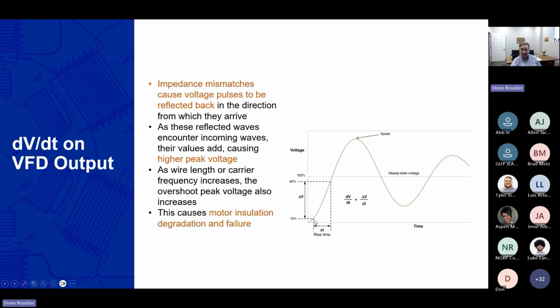dV/dt. I'm thinking that most of you have seen a motor failure, heard of a motor failure. It really is that the turning on and off of these silicon devices has a very fast rate of rise. And if that waveform gets to the end back to an impedance, it can be reflected back and even double. So where you have a 480 volt VFD being at maybe 650 DC volts, that's what the motor is going to see, a switching on and off of 650 volts. But it can be as high as 2000 volts in the worst case of this phenomenon of reflected wave.